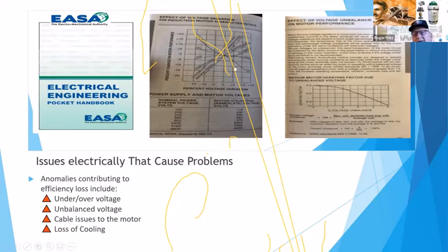And from that, in here, it gives you the derating factor. So it's an area that gets overlooked, especially in irrigation, where we're out in a rural location, you don't get good voltage balance. And if it is off, the chart shows that it's off by 5%. That is pretty common, but for the actual derating factor on the winding, its length of reliability to maintain its original design point, you should derate that motor by 25%. And that doesn't seem to be happening a lot. A lot of times everybody's running it into the service factor. And so the motors tend to run hot. That's on the voltage imbalance.